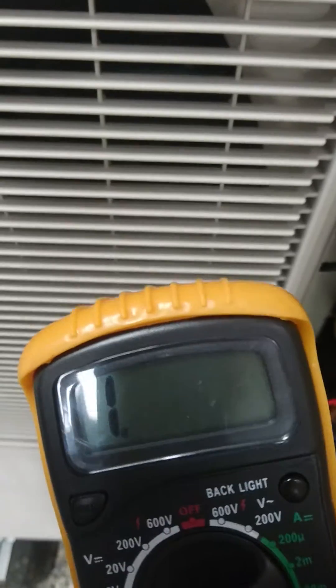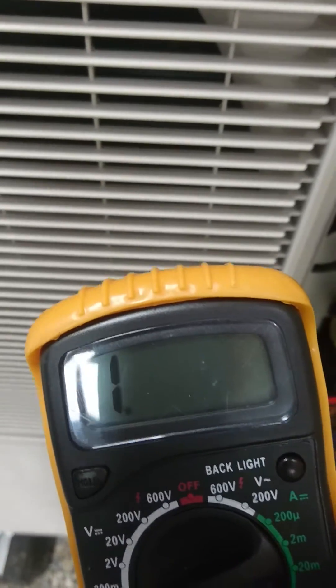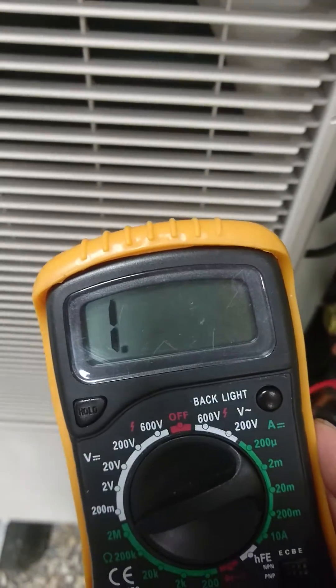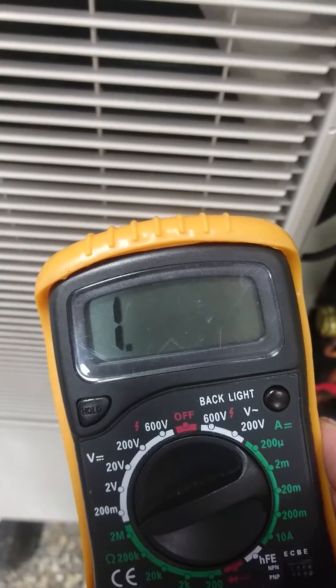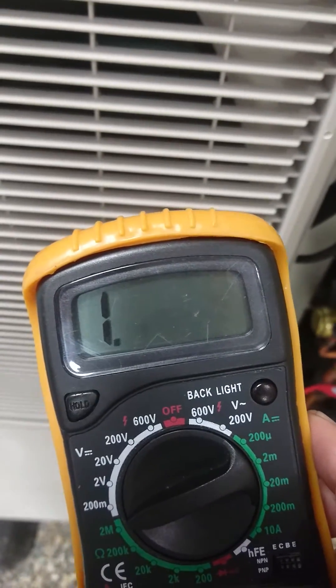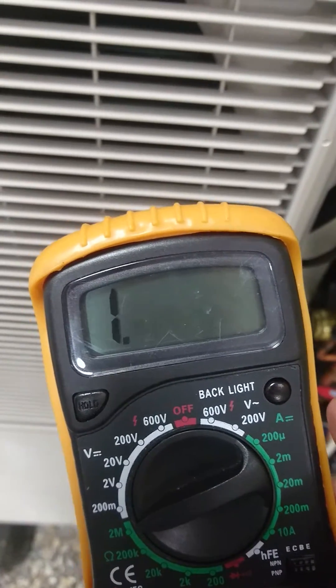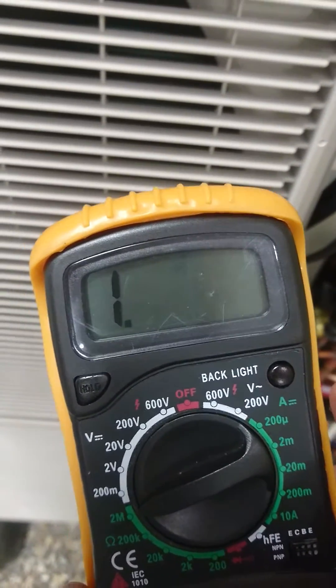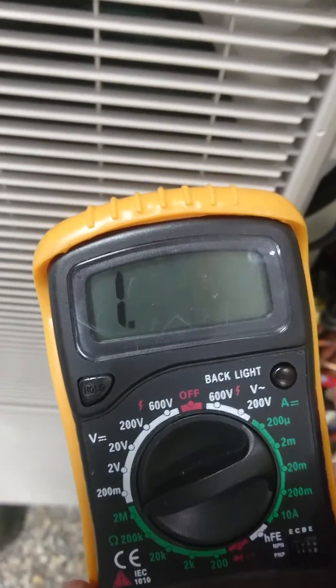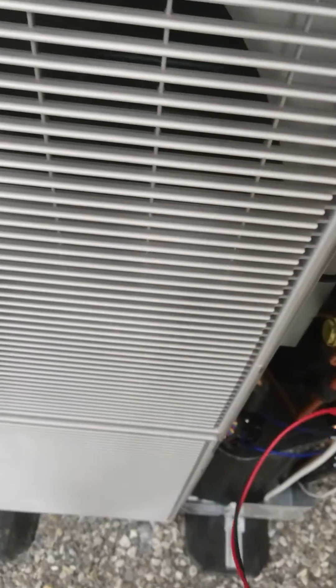And when we go to our multimeter, what we'll find is that the resistance is incredibly high, in this case over 2 million ohms. If the figure falls below a million ohms, or one mega ohm, it means that the fan motor is faulty.